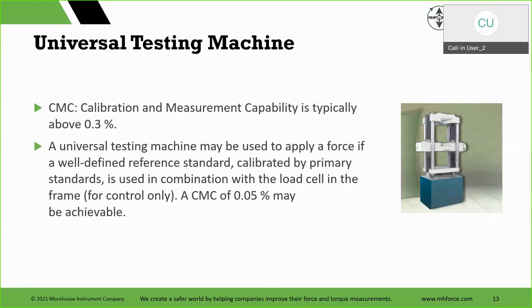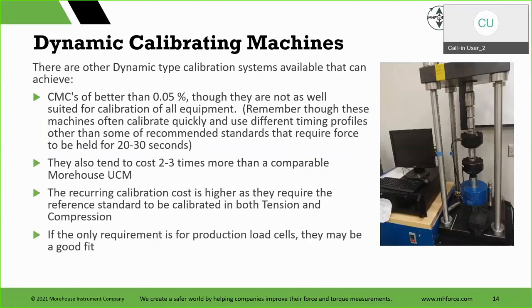Calibration and measurement capability is typically above 0.3%. A universal test machine may be used to apply a force from a well-defined reference standard. That means you put a load cell in there. The machine by itself is not good enough to calibrate other things. If you put a reference load cell in it and use the machine to control the reference, you get better, and maybe you can get about 0.05. We've seen labs do that. Not the greatest way to do the cals, but it would work if you're really on a budget and want to use a dual purpose machine.